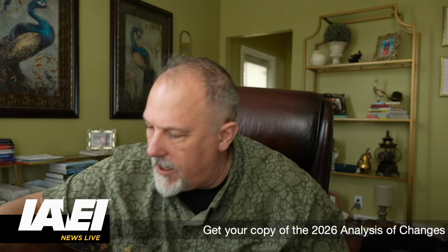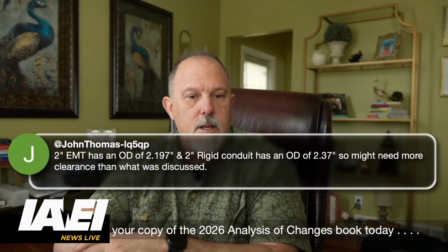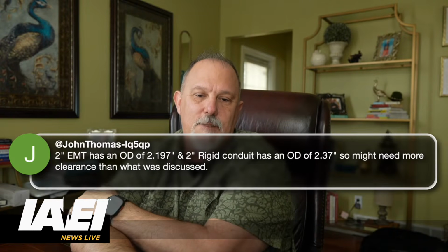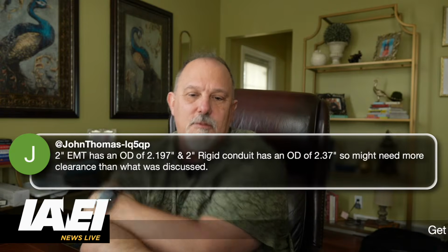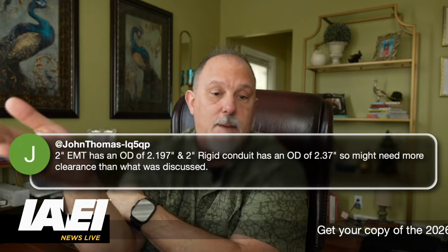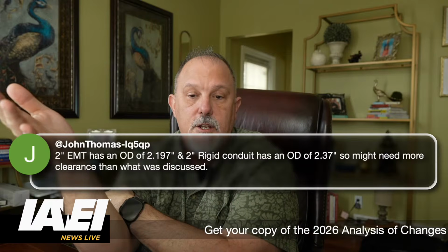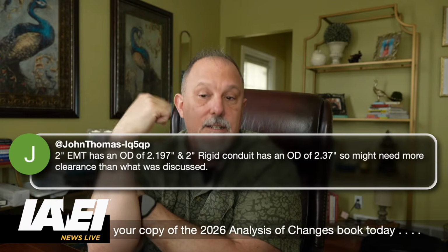Oh, we got another one. John, let's talk. 2 inches of EMT has an outer dimension of 2.197, and 2 inches of rigid conduit has an OD of 2.37. So I would say 2 inches, you would not be able to do that, right? So might need more clearance, yes.